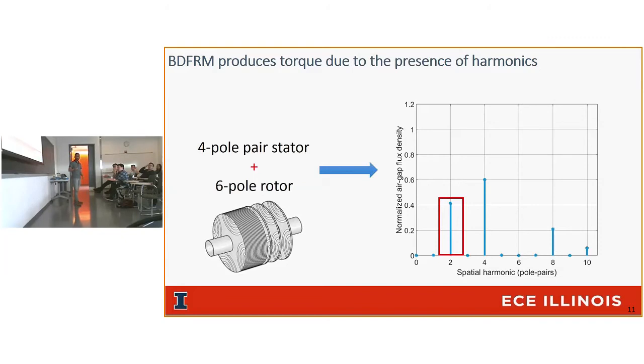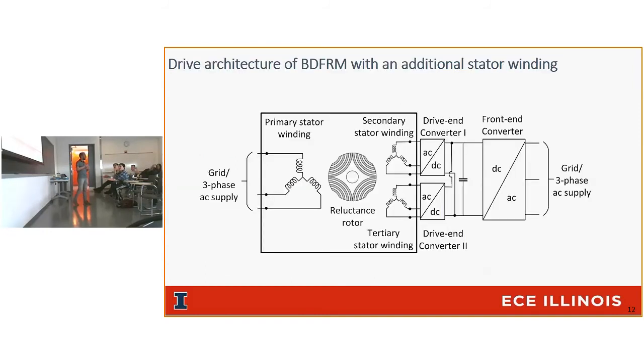So what we can do is have a tertiary stator winding in the same stator slots, which is of 8-pole pair. If we have another stationary winding which can interact with this harmonic, we will be able to generate some amount of extra torque out of the machine, since we will be utilizing this component for the production of torque as well. So how do we do that? By the introduction of another winding.